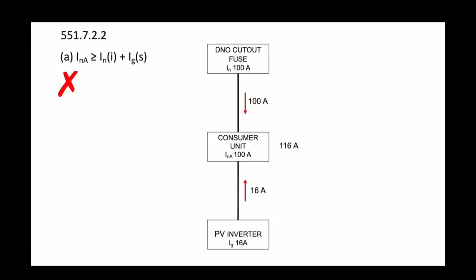So if we look there, we've got a consumer unit rated at 100 amps, the DNO cutout at the top also rated at 100 amps, and the PV inverter rated at 16 amps. So effectively, we could be pulling 116 amps through that consumer unit, and it's only rated at 100 amps. We're going to ignore fusing factors, we're just going with this as we've gone through. Makes sense, doesn't it? That enclosure, however rare it would be, has only been designed to carry 100 amps. It's going to cause a problem.